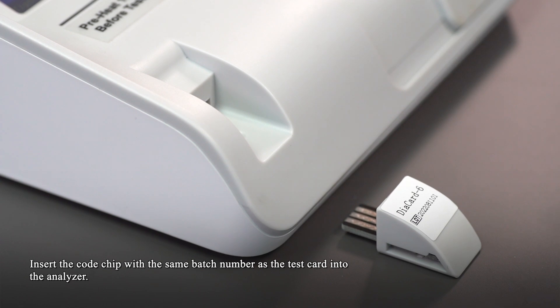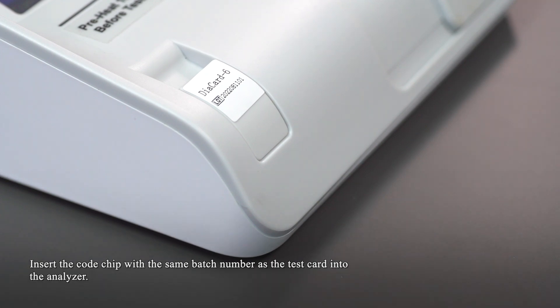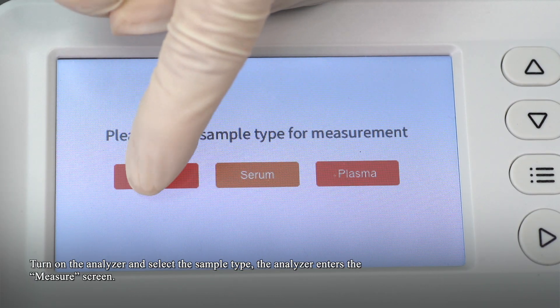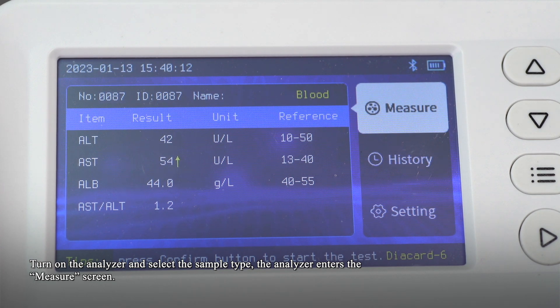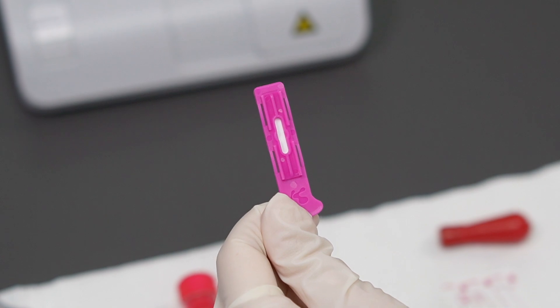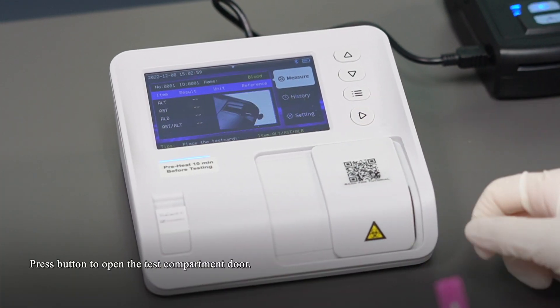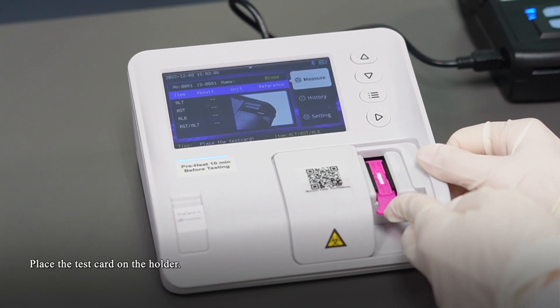Select the code chip with the same batch number as the test card and insert it into the analyzer. Turn on the analyzer and select the sample type. The analyzer enters the measure screen. Press the button to open the test compartment door and place the test card on the holder.